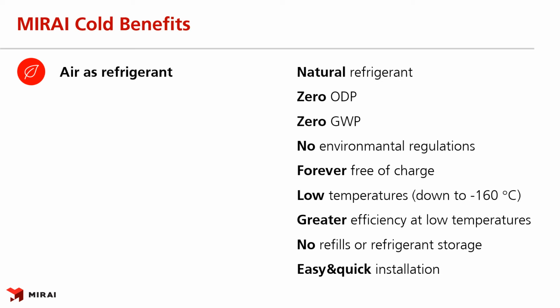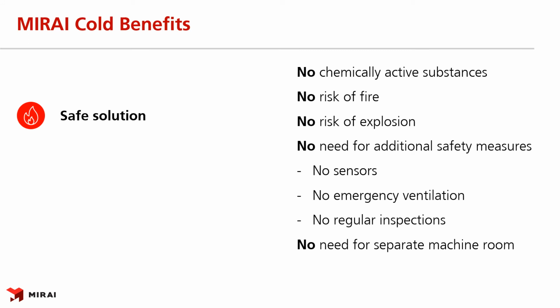When the site is prepared for our machines, it will take only 45 minutes for a closed cycle machine or 4 to 5 hours for an open cycle machine to be up and running. Using air as a refrigerant provides maximum safety possible. There are no chemically active substances, mainly compared to systems using refrigerants category A2L and higher. There is no risk of fire or explosion. Also related to refrigerants category A2L and higher, or even CO2, there is no need for additional safety measures like sensors, emergency ventilation, and regular system inspections. With all that considered, Mirai Cold does not require a separate machine room.